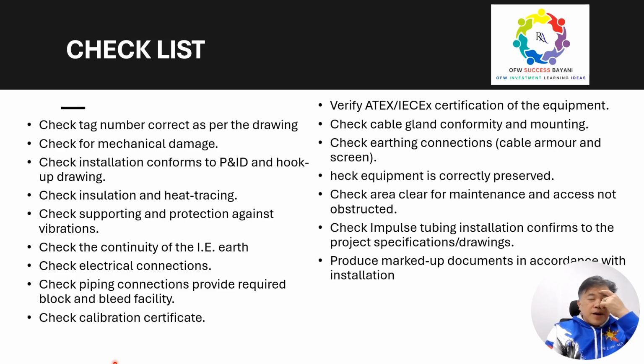Okay, and another one, verify any ATEX certificates or IECEx certifications, check cable gland conformity, and check earthing connections. Check equipment's correct preservation, check area clean, maintenance access not obstructed, check impulse tubing, because we have an impulse line tubing that we need to install to connect our pipe, valves. Okay, mark up any red lines to be done during your inspections or during any of your activities at site, either pre-commissioning, or during inspections from the quality, and also during your handover prior to proceeding to our commissioning team.